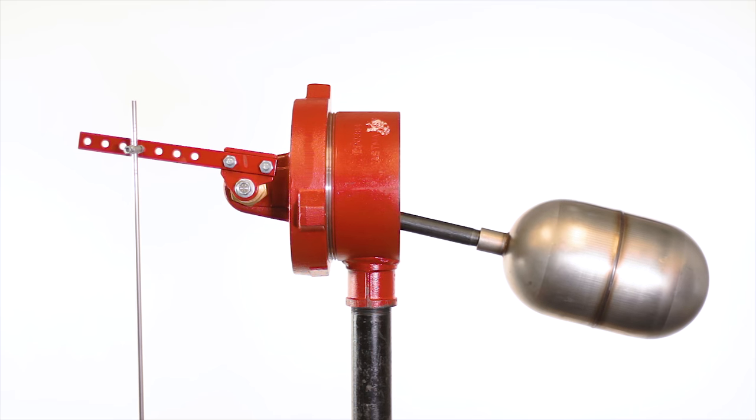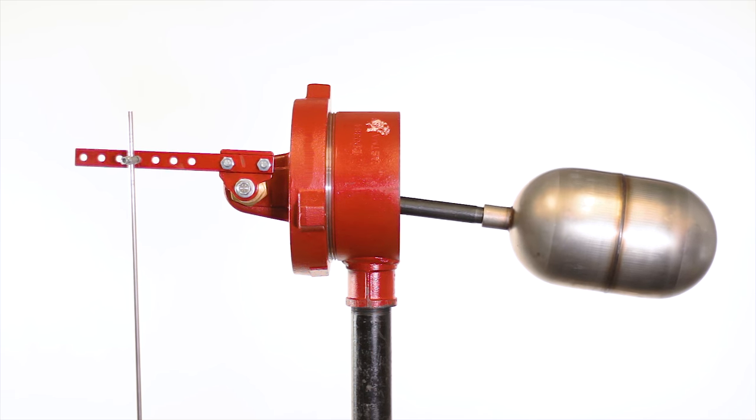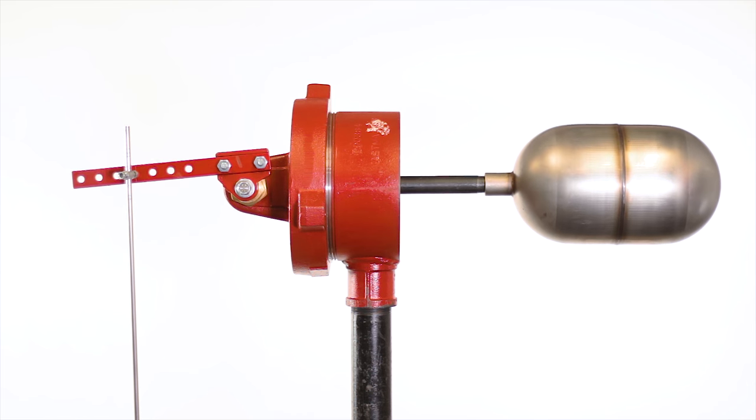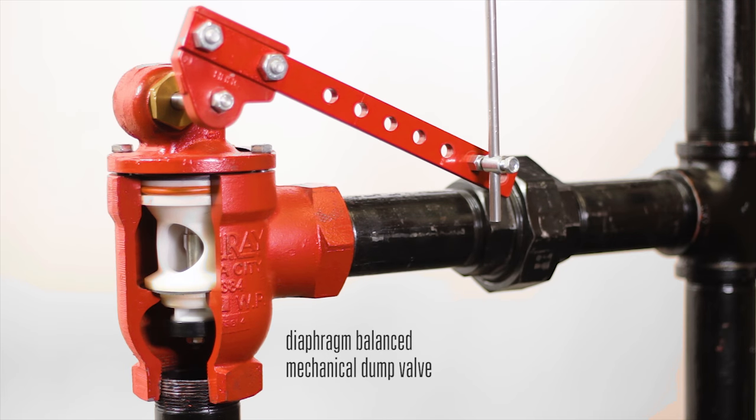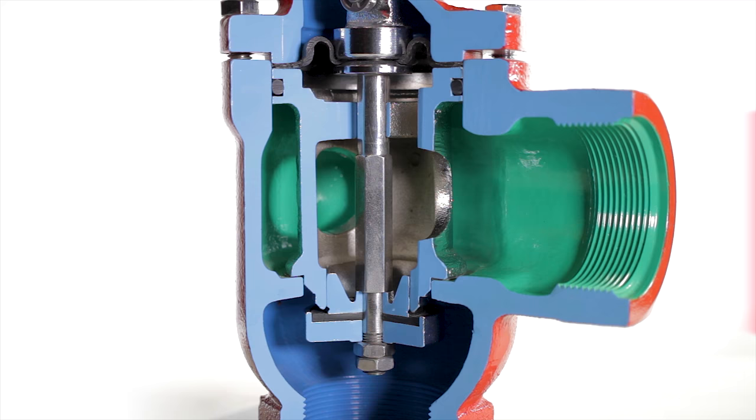As the liquid level in the vessel begins to rise, the float moves upward, forcing the trunnion lever downward. This pushes the valve lever down and opens the valve.